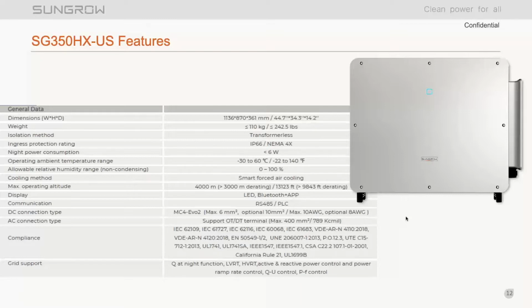Some of our competitors out there and other string inverter manufacturers just have C4 protection, which is more than enough for most projects. But when we incorporate C5 anti-corrosion rating into the powder coating and some of the materials and gaskets that are used to protect the electronics of the inverter, it really does expand the diameter of your installation, right? So you can start looking at projects that are more coastal, looking at projects that may be in a caustic environment like wastewater treatment facilities or landfills, places like that.